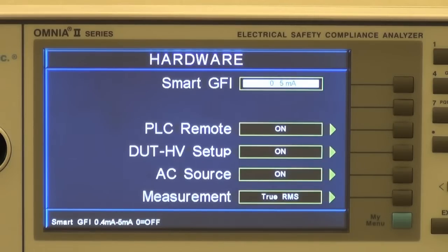Press the DUT HV setup soft key and this will toggle the DUT HV setting between on and off. Selecting the DUT HV to off will prevent the parameter from appearing on the AC or DC withstand and IR test parameter screen.